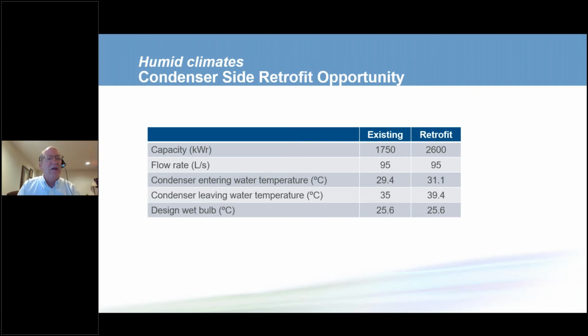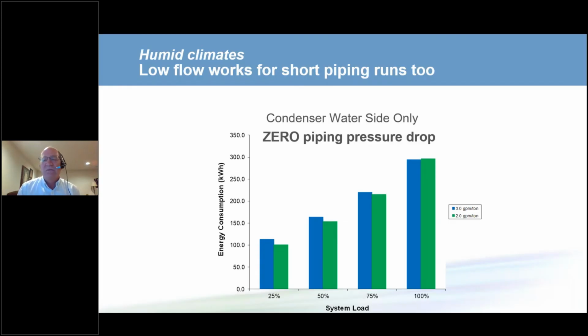The final question people ask is, does this work even if the piping runs are short? Because if the piping runs are short, the pressure drops aren't very high, the pump savings aren't as much. Well, what we did in this case is the bars on the left-hand side are the old flow rates. The bars on the right side are the ASHRAE GreenGuide flow rates. And I told you there was a slide where we talked about the assumptions, and I told you the numbers were wrong because they assumed some particular pressure drops. So we said, well, if they're wrong, how wrong can they be? How low can the pressure drop be?